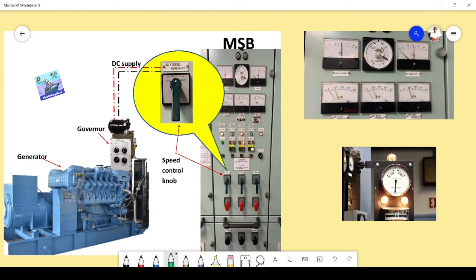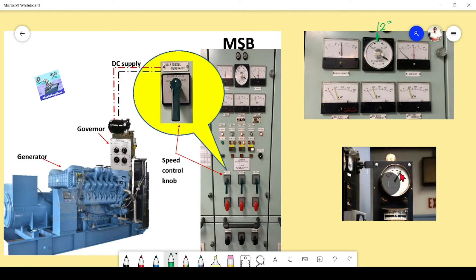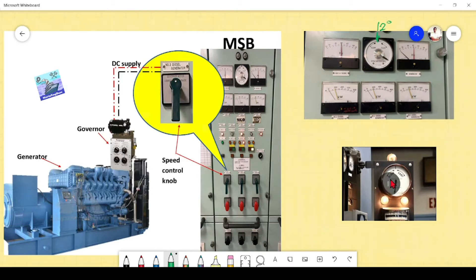This position we call the 12 o'clock position. You can see when the pointer comes to that position, these two lamps are darker. We can also see fast and slow written here. If it is turning clockwise, it means your incoming generator is running fast, slightly higher speed.